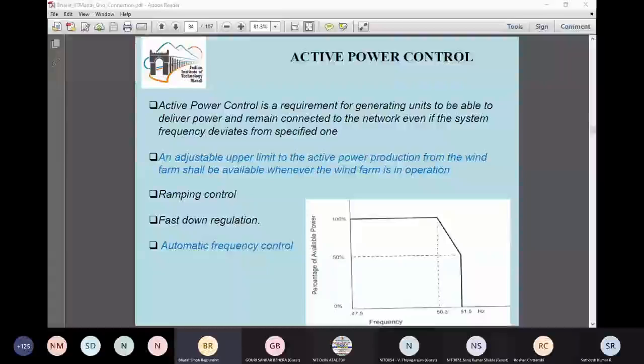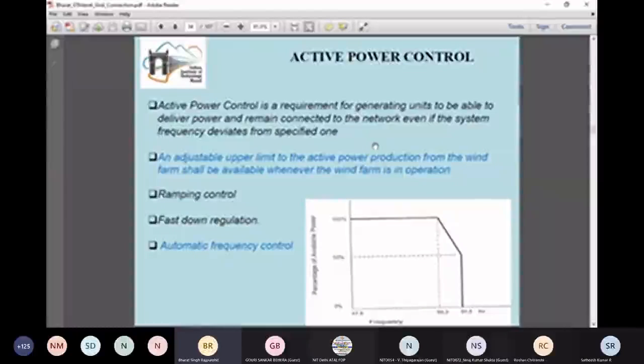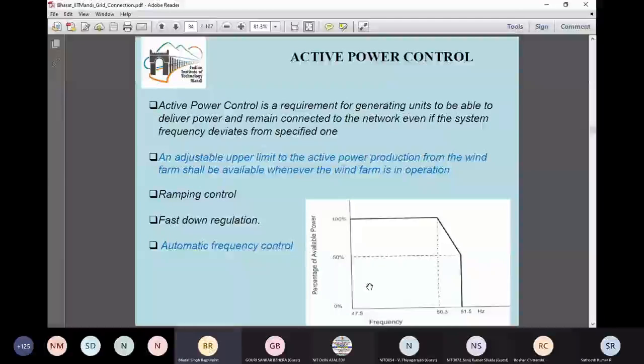So the power which is coming from the wind turbines is not in our control; it is nature dependent. And as I mentioned in the previous slide, we are already working on the maximum power point tracking algorithm. It means we are utilizing the maximum power available with the moving wind. So increasing the active power is not in our control unless the wind is also able to blow and provide more energy. So that restriction is there. That's why automatic frequency control, where a change in the active power is based on the frequency signal, is very difficult to exercise in this case.